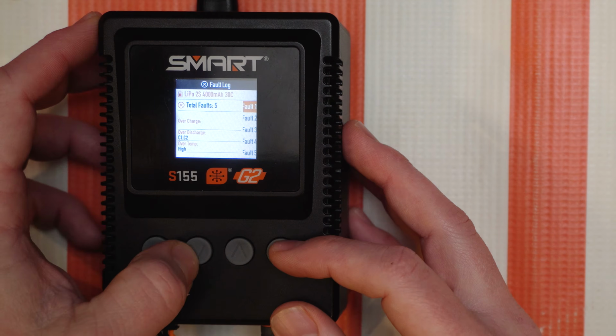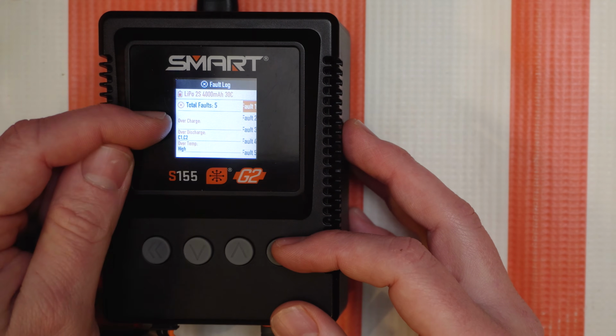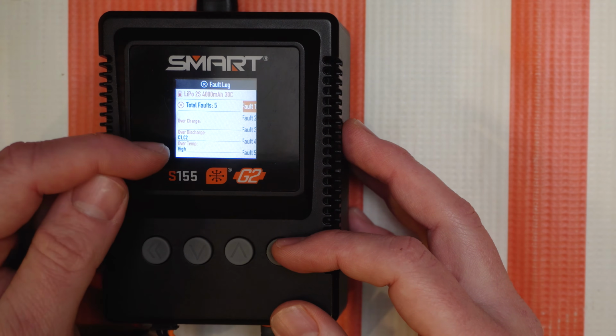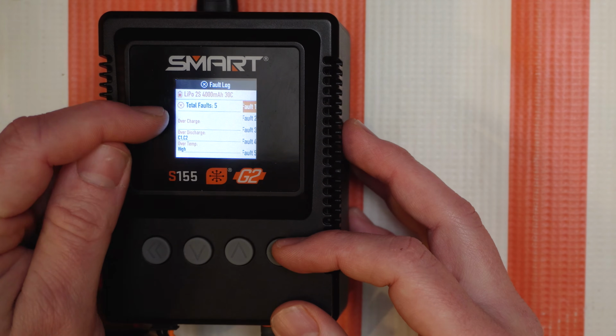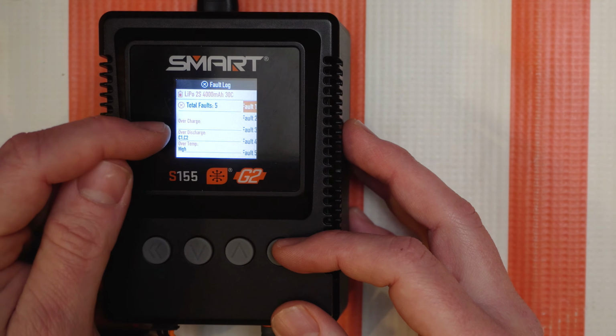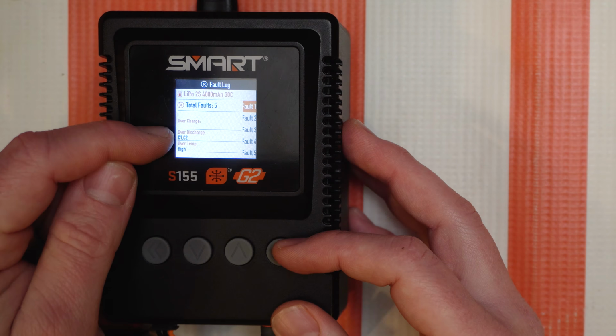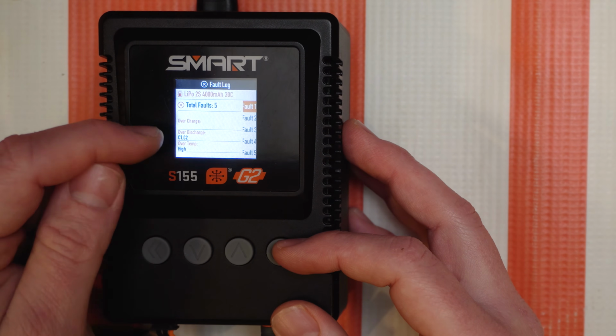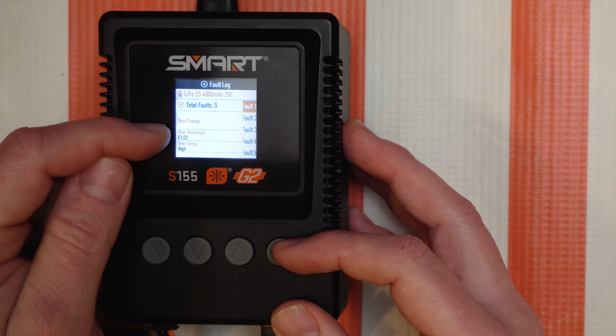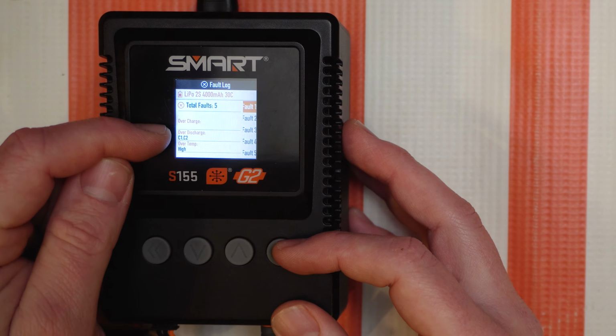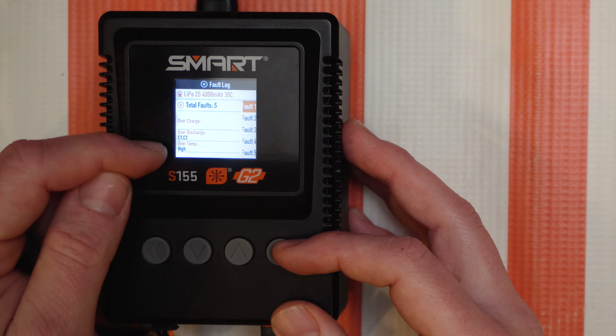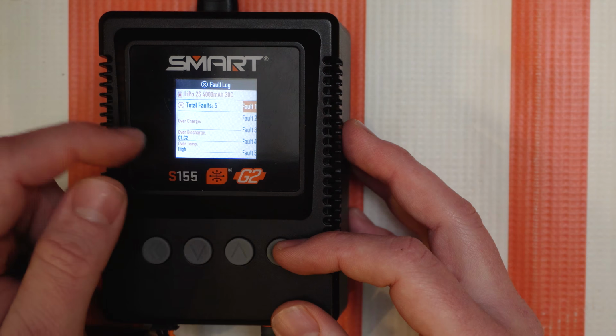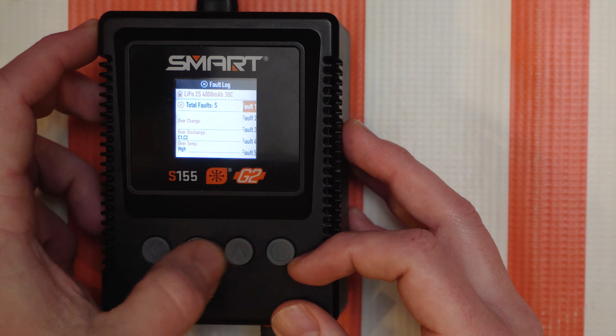So we've got fault 1, and you'll see it says overcharge, over discharge, and over temp. Overcharge, none there, that's good. But I did over discharge cell 1 and cell 2 - C1 and C2 stand for cell 1 and cell 2 being over discharged. It also got too hot, so the battery overtemped and flipped that flag.